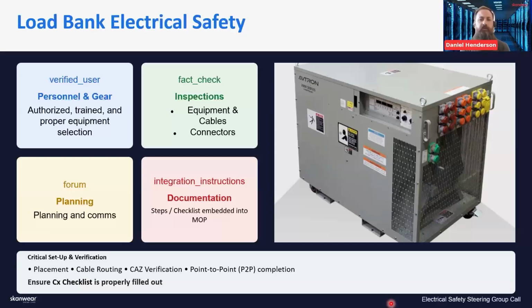It's interesting. At which point did they blow off the cables? Was that when they were energized from the supply? That's what I was told. It was energized from the supply, and then they heard it at the load bank. And then when they turned, you could see one phase of the cable conductor popping off the ground.